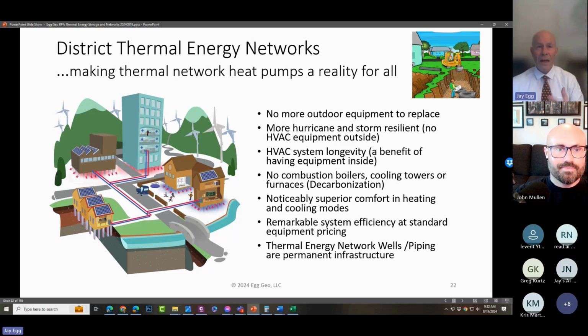We know that's impossible, you can't have that. But when you're sharing energy between buildings, especially in the dead of winter, you're approaching such a load diversity that it's impossible in any other scenario except in a thermal energy network or shared network of some sort. So here I like to pause and talk about other things geothermal or thermal energy network communities can boast that you can't get from air source heat pump communities. There's no more outdoor equipment to replace, which is a huge benefit. Coming from Florida, when we did coastal applications—commercial or residential—even with sea-coast coated coils, those units were lucky to last 7 to 10 years.